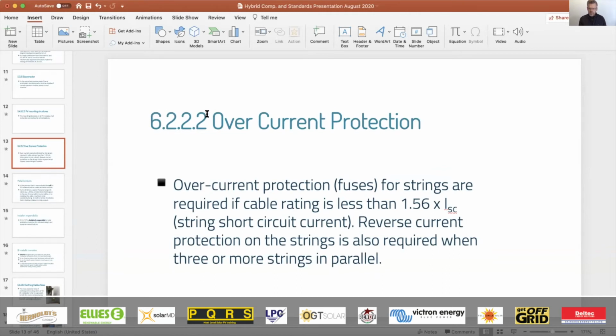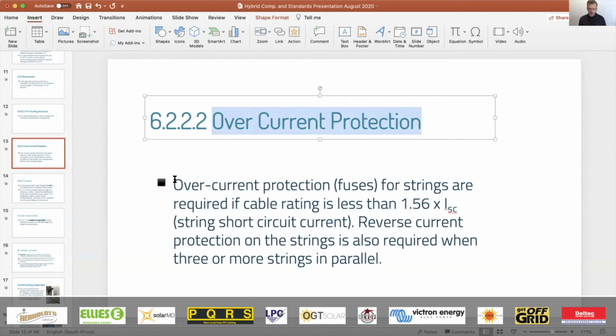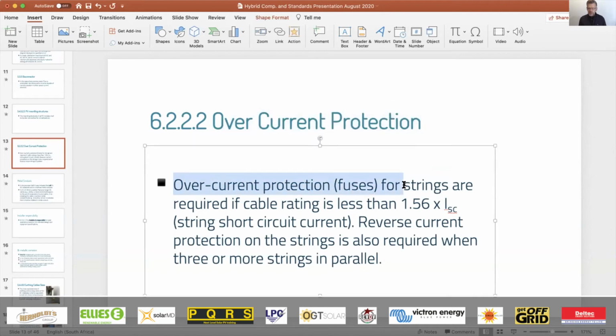Over here, overcurrent protection. So overcurrent protection for strings is required if the cable rating is less than 1.56 times the short circuit current.